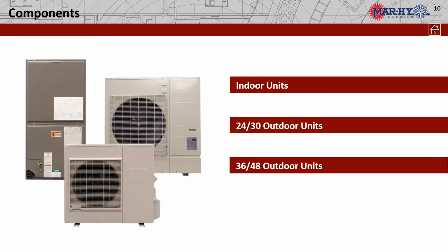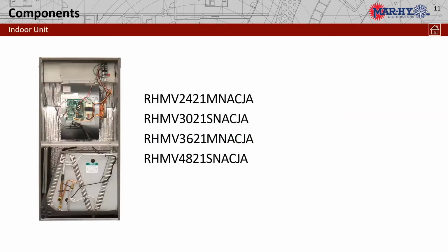All right, let's talk about some of the indoor and outdoor units. So this is what it looks like, the RH-MV2421. One thing you'll notice about all four of these cabinets, they're all 21 wide, and they are very specific to the 17 SEER installation. So when you look at that coil, if you all can see my mouse, this little knockout on the top of the coil, that little plug, depending on the application of this coil, you may have to relocate that return air sensor. We need to be able to sense that upstream of the coil. And I'll cover that a little more in depth as we go through the install of the coils and such.